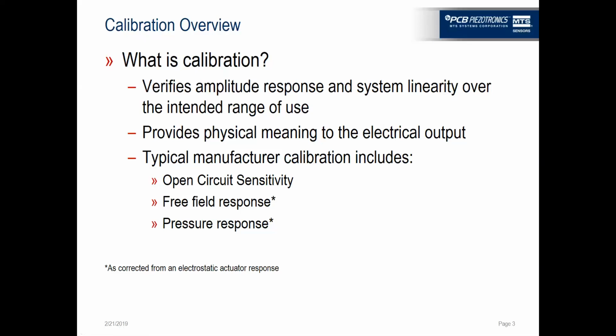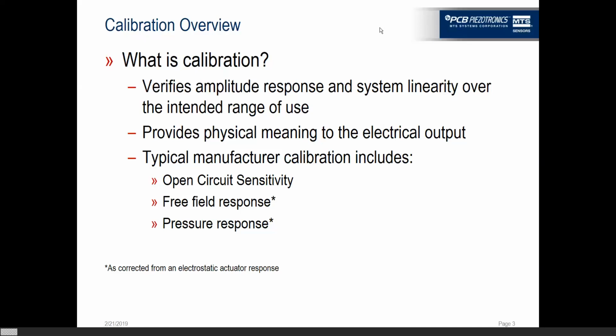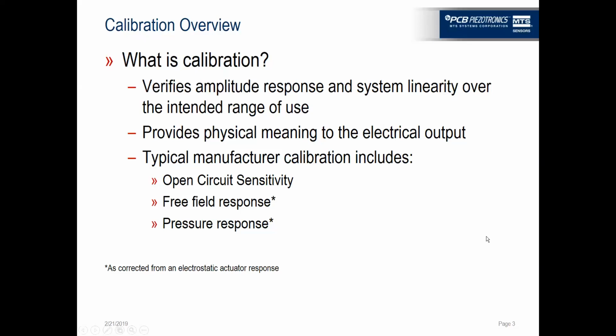microphone. For microphones, a typical manufacturing calibration includes an open circuit sensitivity, meaning for the cartridge, what is the sensitivity of that cartridge just on its own? It also includes either the free field response of that microphone, meaning what does that microphone do in a free field, or the pressure response of the microphone, meaning what does that microphone do when used in a coupler or mounted flush to a wall. As you see by the asterisks, in many cases, these two responses are developed and corrected from an electrostatic actuator response. And I'll talk about that a little bit later on in the presentation.